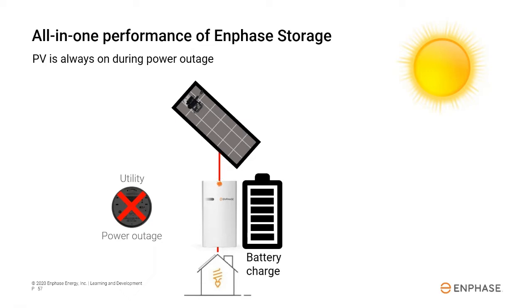All battery storage systems must be able to curtail the power output of the solar PV during a power outage, even with a maximum ratio of 1.5 to 1 that we discussed earlier. If the battery is full and the home is using little power, the power from the PV system has nowhere to go, and it could cause instability in the microgrid, and the battery system could shut down.